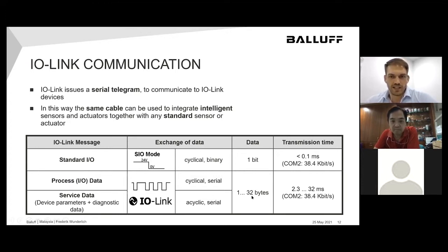In total, the data can be up to 32 bytes. So it's a lot more, obviously, than a standard input-output. And therefore, the transmission time also increases. If you use the full data volume, it can be up to 32 milliseconds of transmission time.